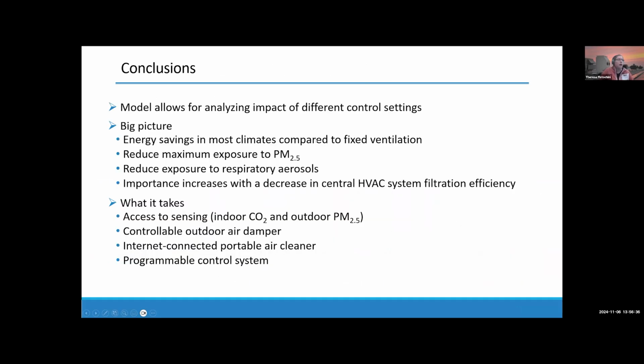So conclusion, there's energy savings in most climates compared to fixed ventilation. The big deal is we reduce maximum exposure to PM 2.5. We also reduce exposure to respiratory aerosols, and these differences are more significant if you're using a lower filtration efficiency. All we need is a controllable outside air damper, some access to sensing, an internet connected portable air cleaner, and a programmable control system.